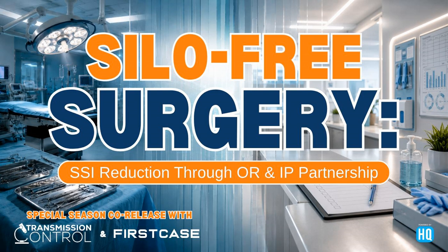We challenge the IFUs using worst case considerations. So we're looking at reduced soak times, reduced flushing volumes, detergent dosage, soiling the devices more than what they would see during clinical use. So I'm adding more blood, more tissue to simulate those worst case conditions. And then real world hospital practice is essential to understand whether the IFU is feasible or not. So we as a test lab have taken the step to go to our local hospitals and watch them process. And just watching them, we see a lot of gaps of what we didn't do back a few years ago that we have implemented now.